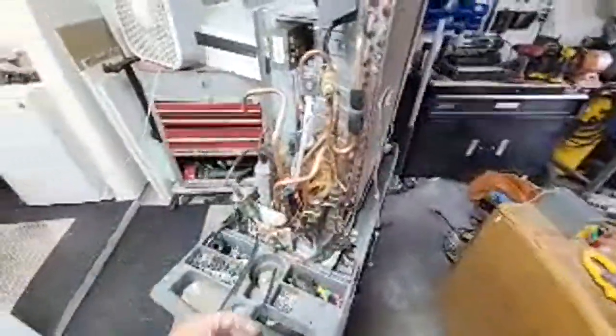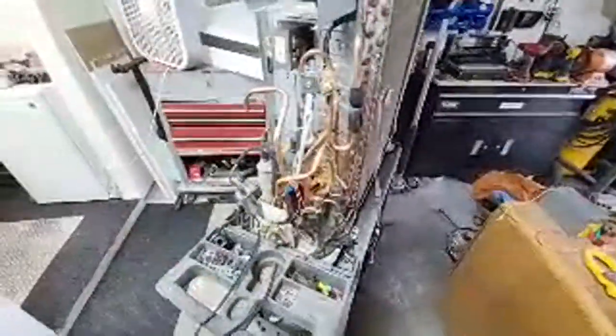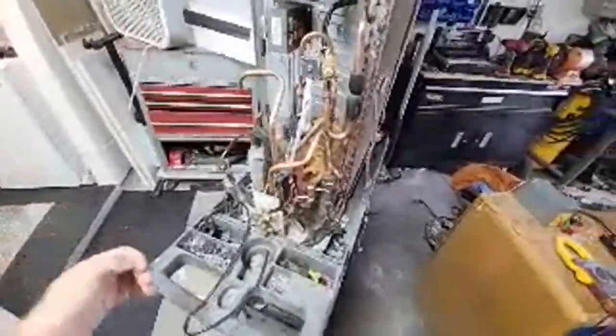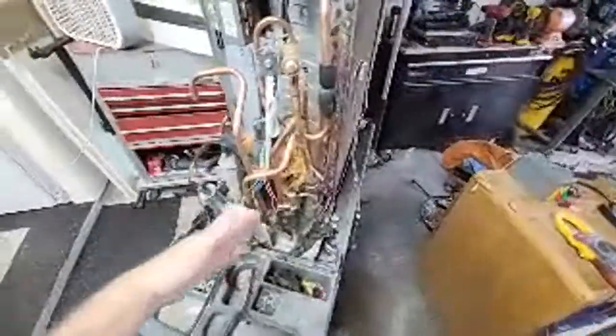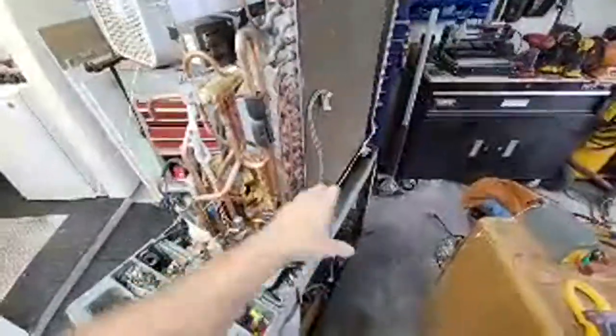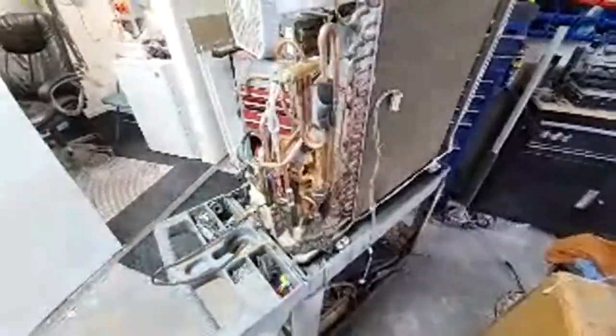And then what I'll do is, like in the summer, I'll just put a thermistor on there and modulate the outdoor fan. When the water starts getting really hot, towards 130 degrees, it'll still be at least 130 at the liquid line. Then I'll probably try to drive it down a little bit, so it'll modulate this fan just a little bit and bring it down a little more, subcooling it before it goes as liquid into the indoor unit.